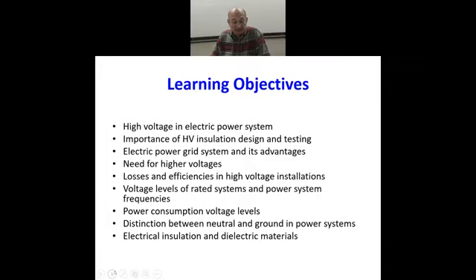I talked about the importance of high voltage. Then, why do we need higher voltage? You know that the power rating, W, real power, is nothing but V into I, if we consider the cos phi or the power factor to be ideally unity, I would say ideally 1. So it is V into I. So if you want to increase the power rating of any apparatus or installation, what do we need to do? We cannot increase the magnitude of the current indefinitely. But we have been able to increase the magnitude of the voltage practically indefinitely.